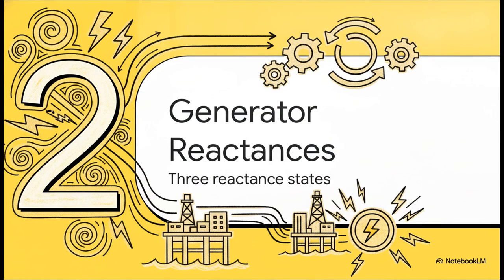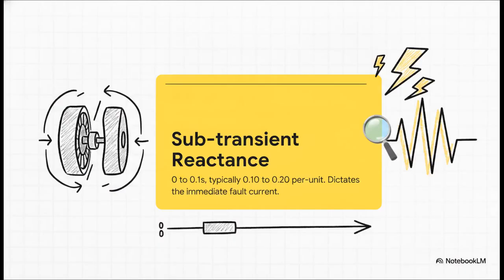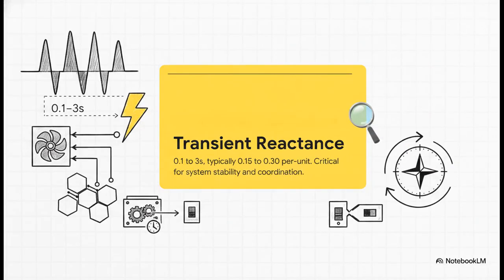Moving right along to Section 2, generator reactances. We have 3 distinct states here. When a fault strikes, those first few milliseconds are literally violent. From 0 to 0.1 seconds, the subtransient reactance is at its absolute lowest, usually hanging around 0.1 to 0.2 per unit. Because this resistance is just so incredibly low, this state dictates your immediate, absolute highest peak fault current. If you're out there sizing circuit breakers to survive a massive explosion of short-circuit energy, this is really the only number that matters.